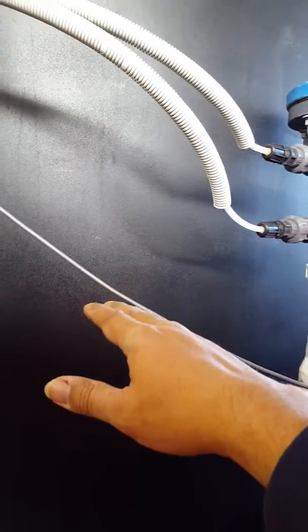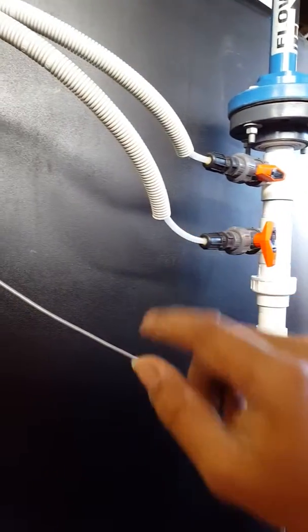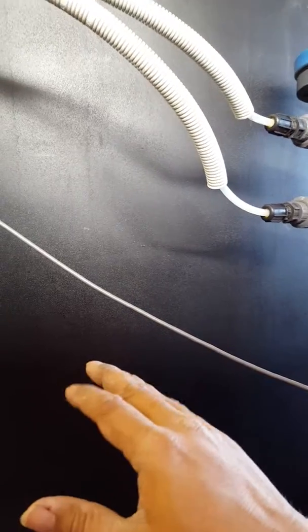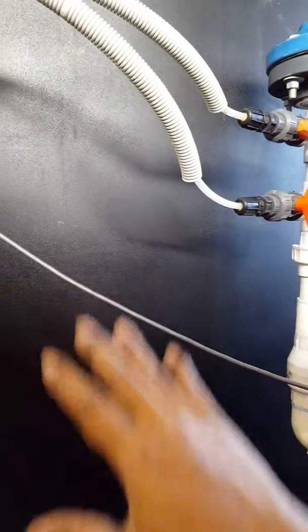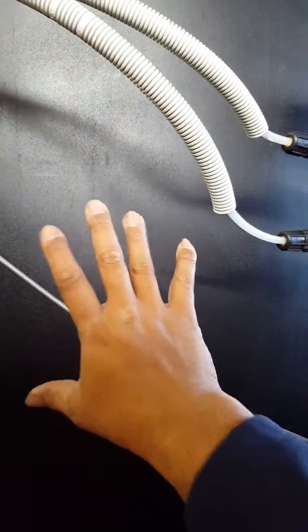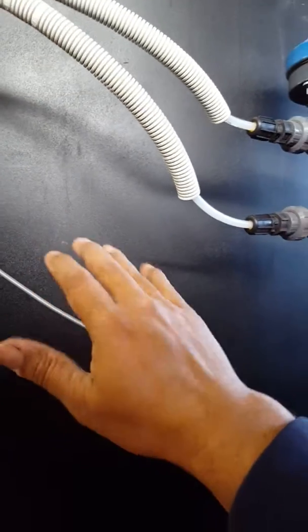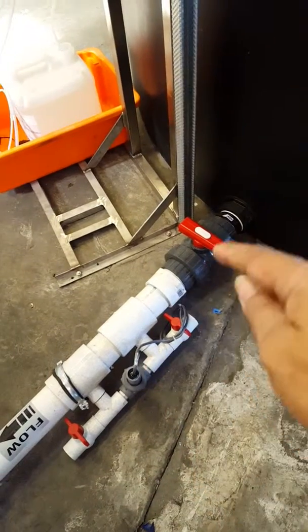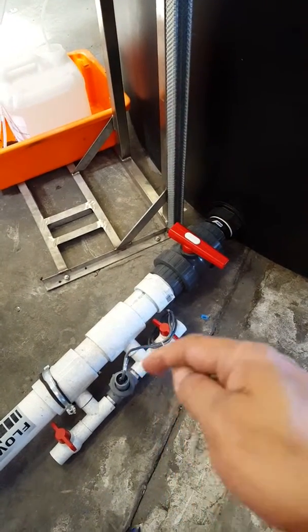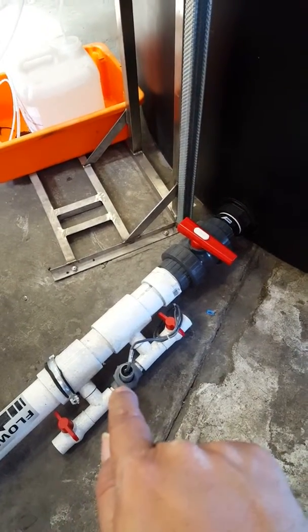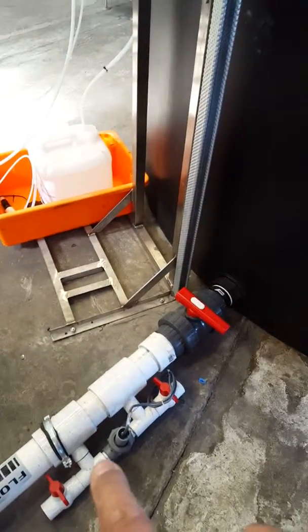So if there's a pH of 10 going into the tank, then this will keep going until it gets down to 8.3, and then the pumps will all turn off, and that means the wastewater in there will be between or under 10. This probe down here, when we open the valve, is going to measure what's going out, and that's the one that we're going to capture and record from our data log, which I'll show you in another video later.